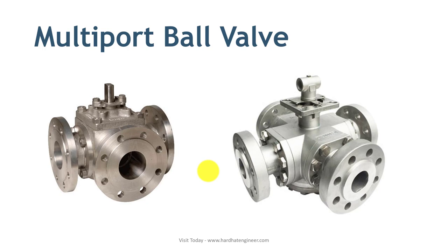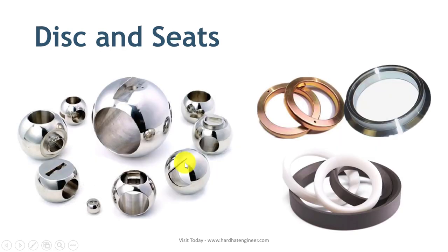On this slide, you can see the ball and the seat. Ball valve seats are available in both metallic and non-metallic materials. The selection of trim material depends on the service fluid type, pressure, and temperature. A ball valve used in a fire-safe environment is equipped with metallic seats.